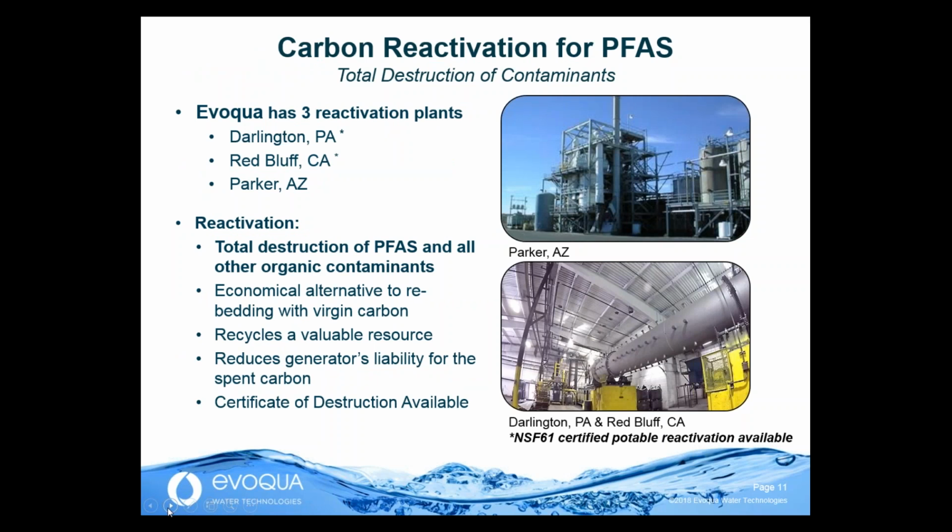So let's further discuss reactivation. Evoqua has 3 different reactivation plants nationwide. Darlington, Pennsylvania, and Red Bluff, California are both NSF certified for potable reactivation. And we also have Parker, Arizona, which is our hazardous reactivation plant. And as I mentioned, the largest takeaway for reactivation in regards to PFAS is that the PFAS that's adsorbed, as well as the other organic contaminants on that surface, are totally destroyed through this process. And if required, a certificate of destruction is available.